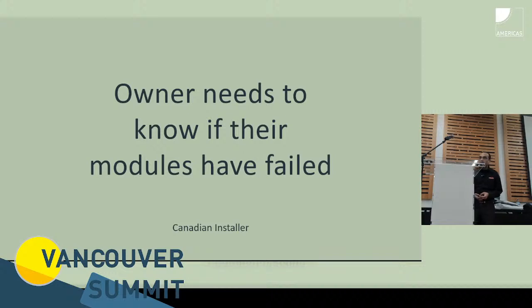Well, over the course of the year, if you look at your annual data, you'll see 25% of your panels not producing because your annual production will be down. Yes and no. The reason is your oversizing will actually mask that for a big part of it. I'm not saying you should accept badly performing panels simply because they're connected to a string inverter. That's not the intention. The oversizing is what's buying you that cushion, masking the issue.